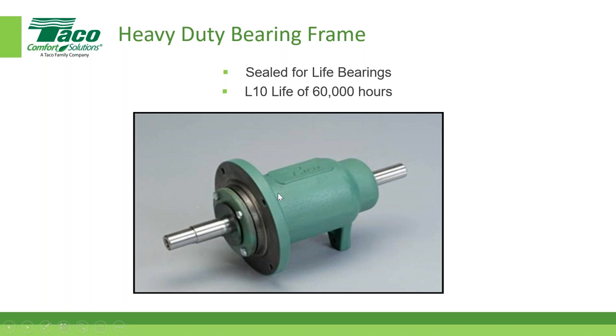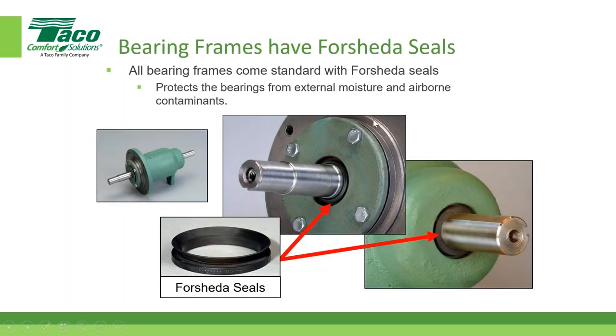You can order it otherwise. So if it's in your spec and some facility, a school or whatever, demands that the bearing frames come with lubricated bearings, you can order it that way. You just need to let the manufacturer's rep know that. So they're very heavy duty. And like I said, there are different sizes of them, as you can imagine. And they do come with a Forsheda seal. This seal sits right in here, because that's obviously a pathway, right? But with that seal sitting in there, that protects the bearings from external moisture and airborne contaminants getting into that cavity. So that is just something that we've standardized on, and we feel pretty comfortable with that.